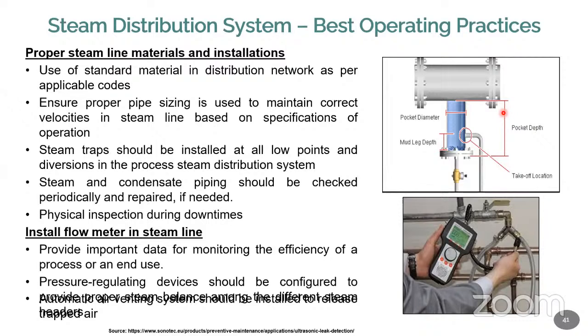Similarly, steam traps are installed at regular intervals at the lower points, not in the main pipe. This is the main pipe, so this is the point mentioned only for steam traps. At regular intervals you will always have downward points available for steam traps, and these should be properly checked and given attention. So a steam trap should be installed at a low point like this.